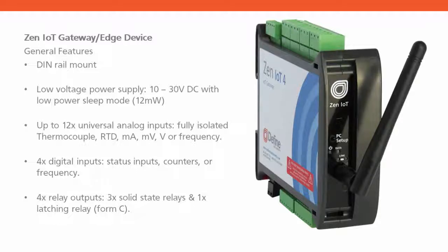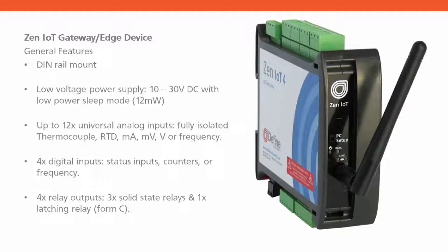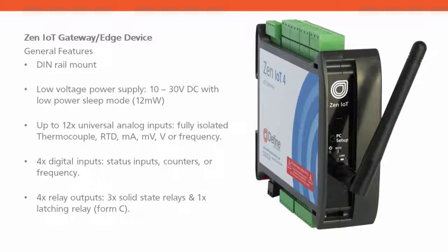It has up to 12 universal analog inputs, each fully isolated and capable of several different modes of operation. It has four digital input pins that can be configured as status inputs, counters, or frequency counters. And it includes four relay outputs, three solid state relays and one latching relay.